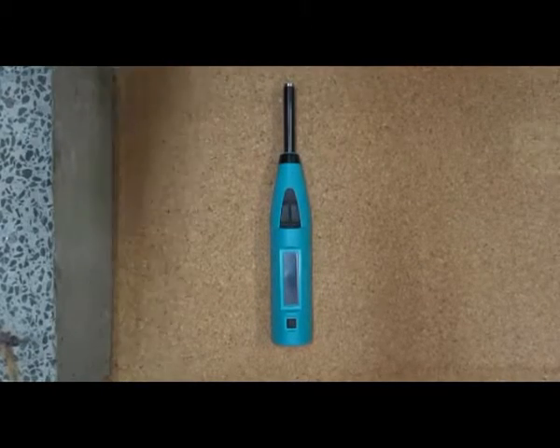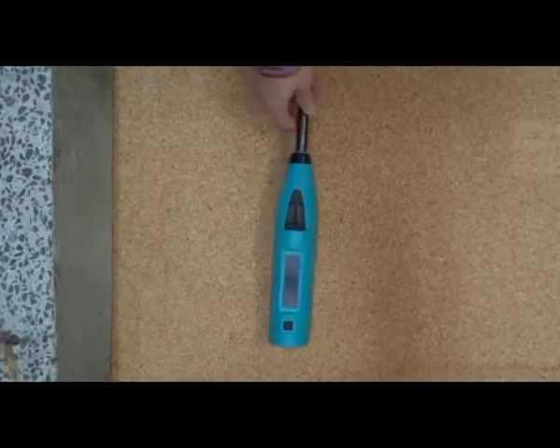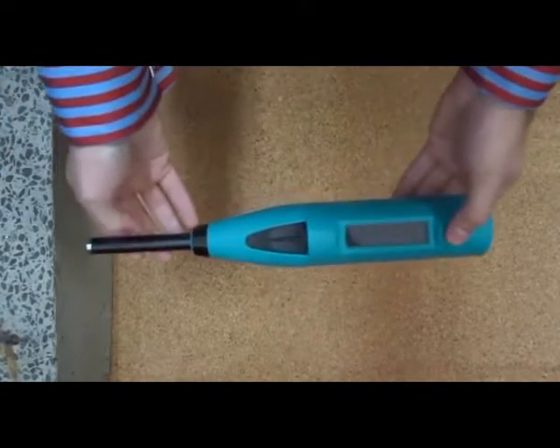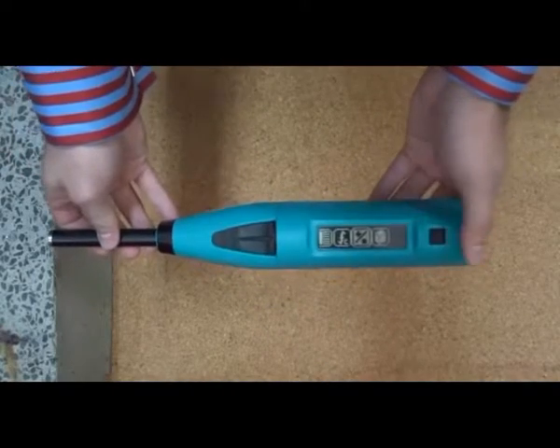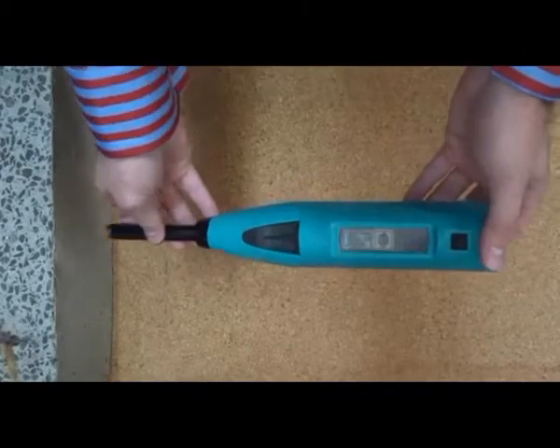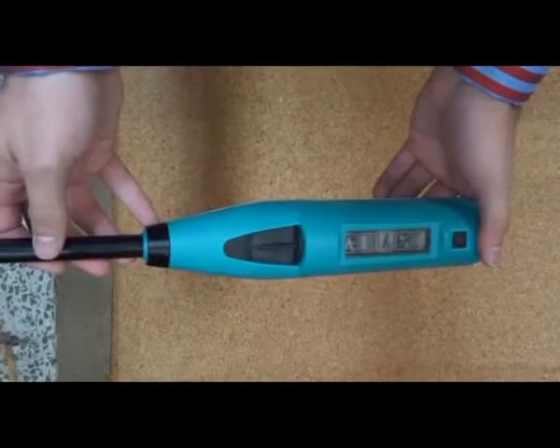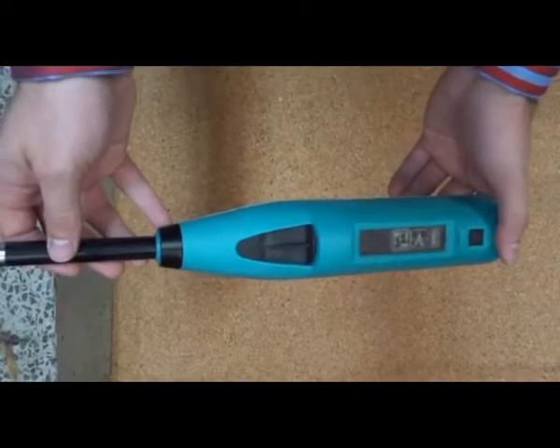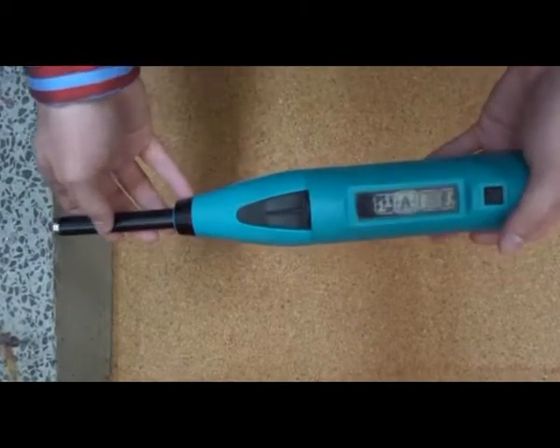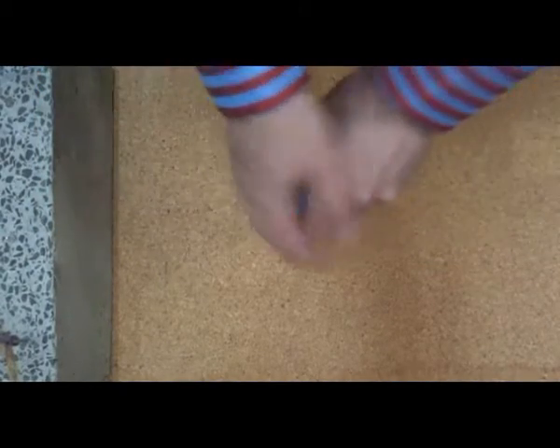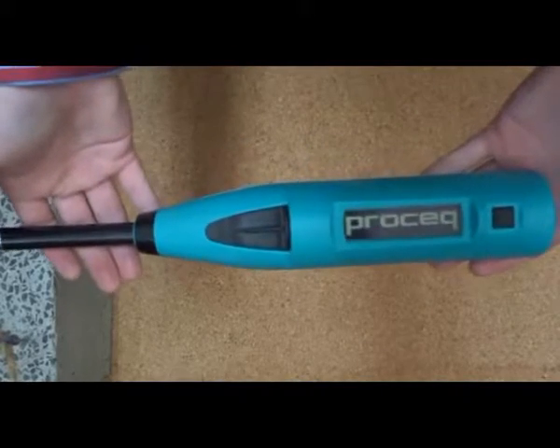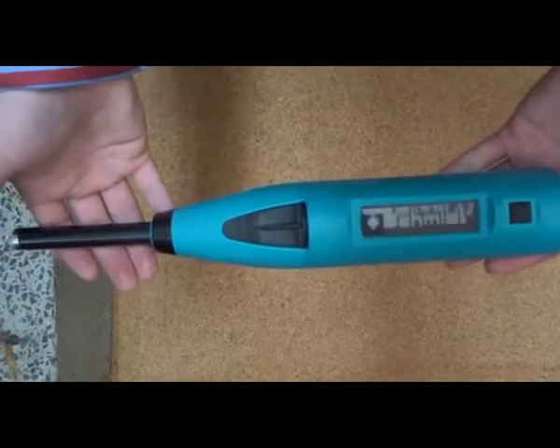The hammer itself is one piece with full data logging and customization capabilities. You can choose custom correlation curves and custom data logging options. The operation is via tilt and a single button, and if you need to reset the device, you press the button and push the hammer to the ground to take an impact and it will reset.